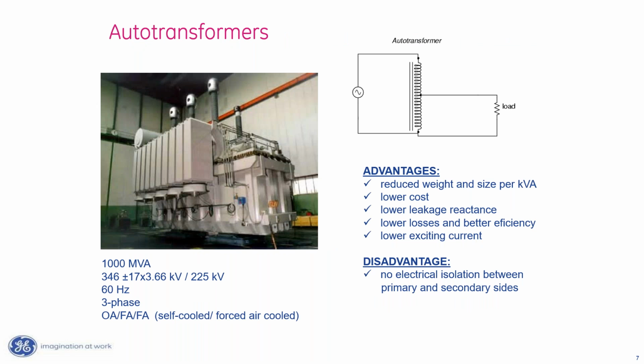Another broad category is an auto transformer. Auto transformers don't have to be just the thing that I think about, but when I think about them, I think about an auto transformer as something that steps down from EHV, extra high voltage, to high voltage in a utility switch yard. So this would be something that goes from 500 kV to 230 kV, or 765 kV to 230 kV, and it's wired as you see here. Now, as you see, the auto transformer is a different thing in that it's just got one real winding. It does sort of have a high voltage and a low voltage winding, but there's no phase shift associated with it. And we don't block any zero sequence currents with this like we do the other guys.